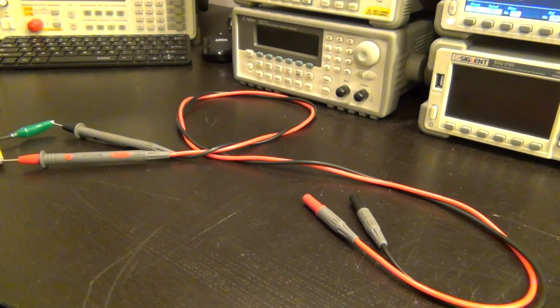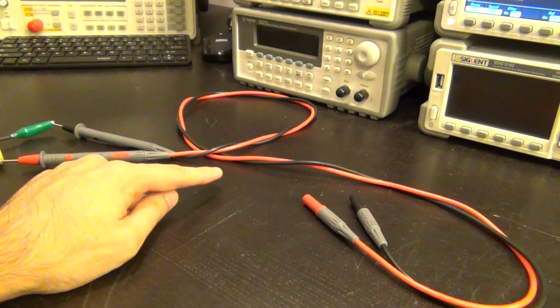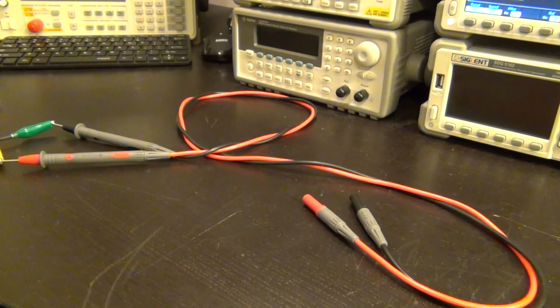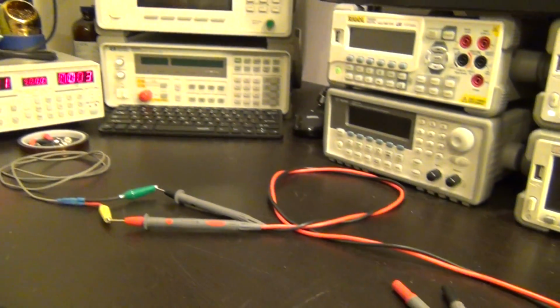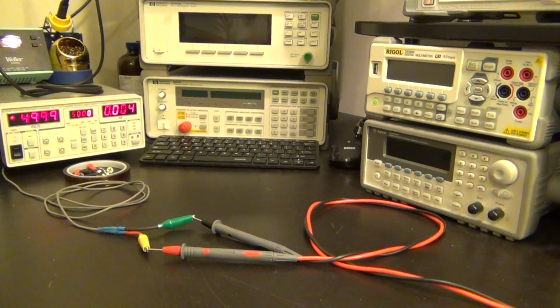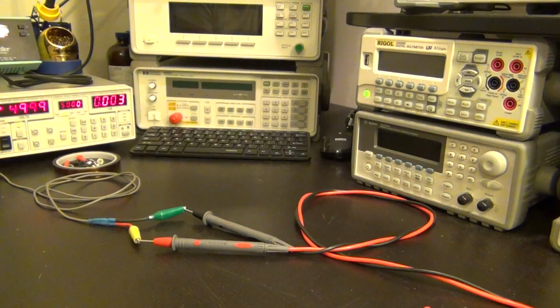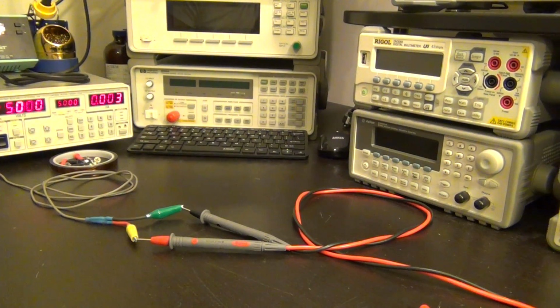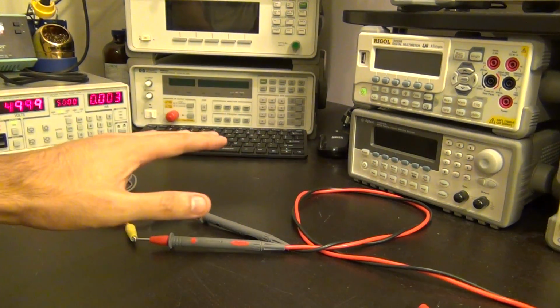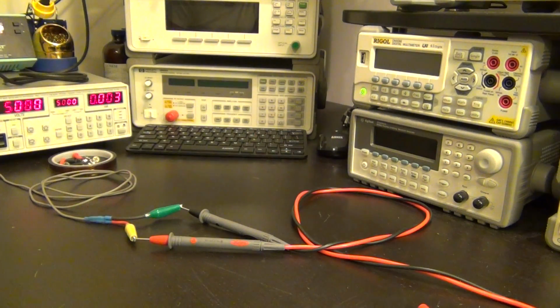This is 5 times the rated voltage, so the electric field between the two halves of the cable is quite high, but it maintains it without any problem. These are high quality cables. I wouldn't worry about them even if you accidentally connect them to very high voltages. Of course, you should never do that because they're not rated for those voltages, but at least the dielectric isn't breaking down.